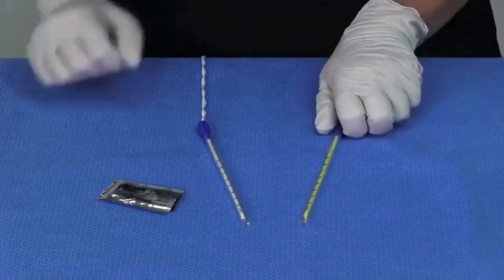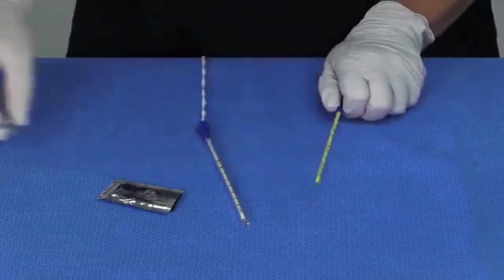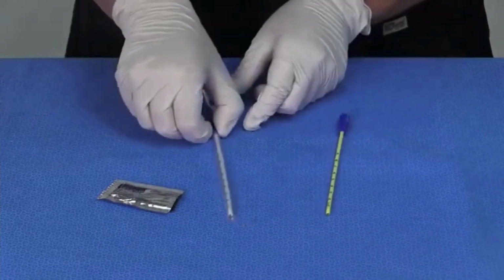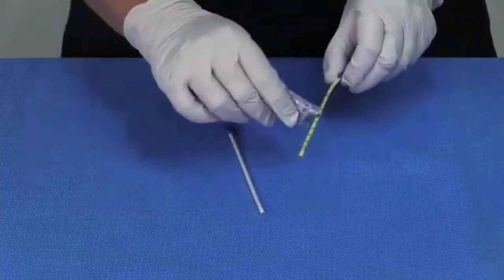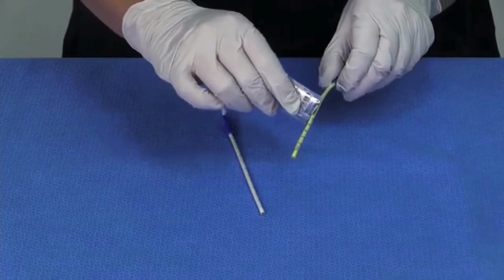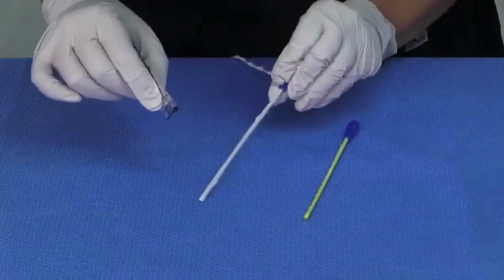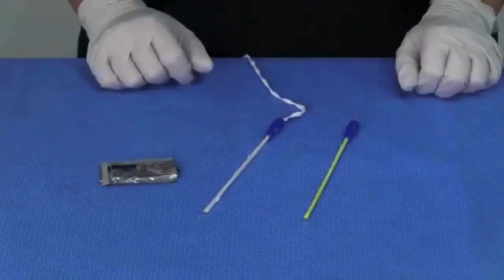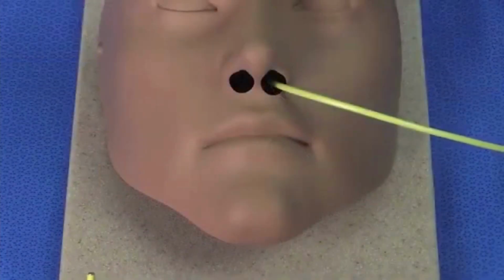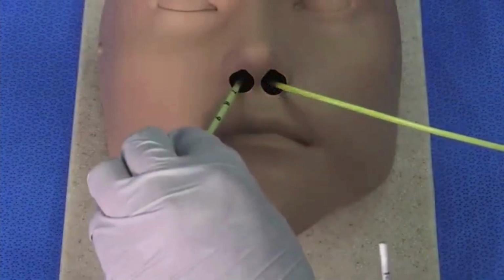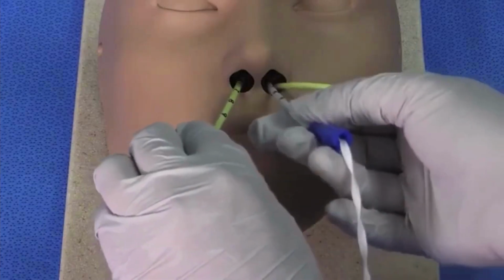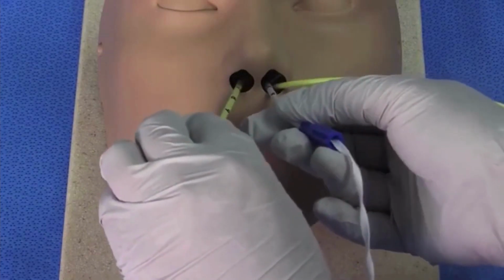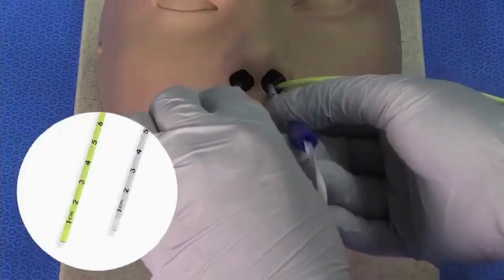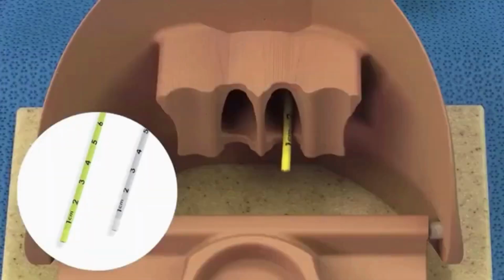First, remove the clear protective sheath from the white and yellow catheters. Then, thoroughly lubricate both catheters with the water-soluble lubricant provided in the package. Avoid lubricating the magnet tips and umbilical tape. Begin by inserting the yellow retrieval catheter to the desired depth into the desired nostril. Then insert the white catheter into the opposite nostril to the same distance as the yellow catheter. Match the printed centimeter markings on the catheter to guide the insertion depth.